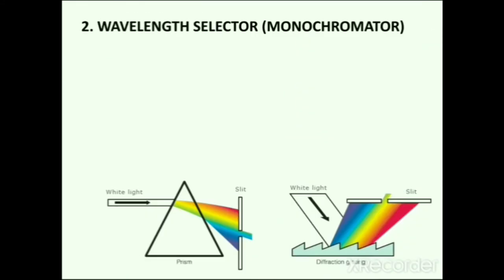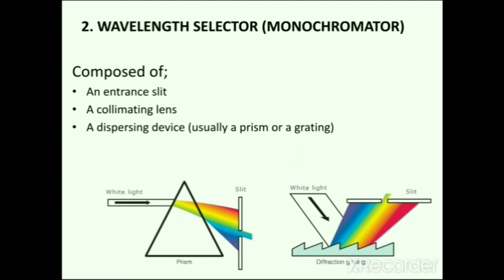Next part of the instrument is the wavelength selector — the monochromator. A monochromator is an optical device that transmits a mechanically selected narrow band of wavelengths of light chosen from a wider range available at the input. It is composed of an entrance slit, a collimating lens, a dispersing device (usually a prism or grating), a focusing lens and an exit slit. Light radiation is passed through the entrance slit and incident upon the dispersing device. The dispersing device converts the light into its constituent wavelengths. The exit slit allows only a single wavelength to pass at one time, so the monochromator converts polychromatic light into monochromatic light.